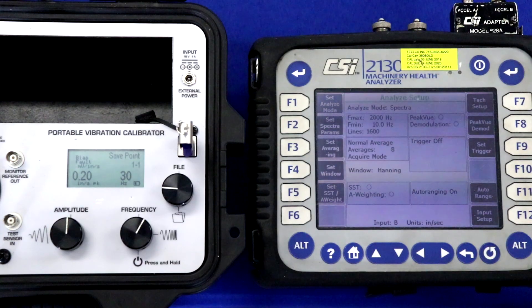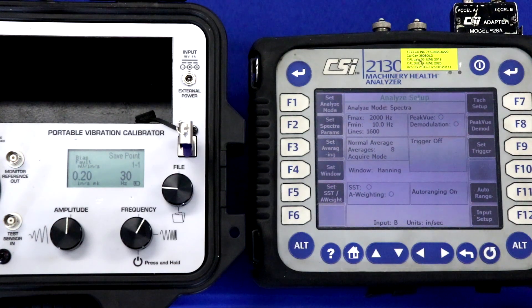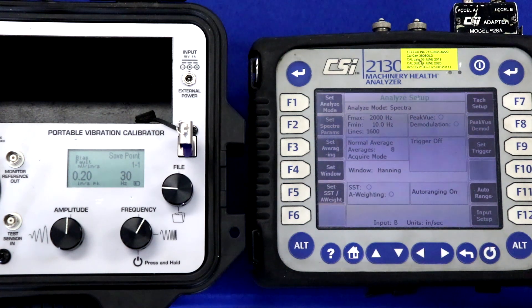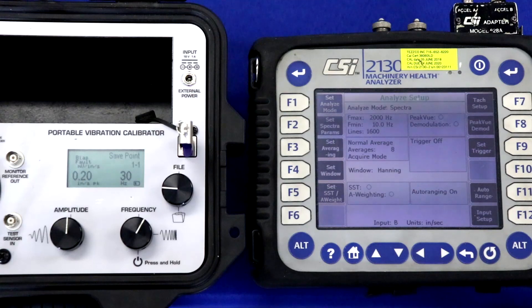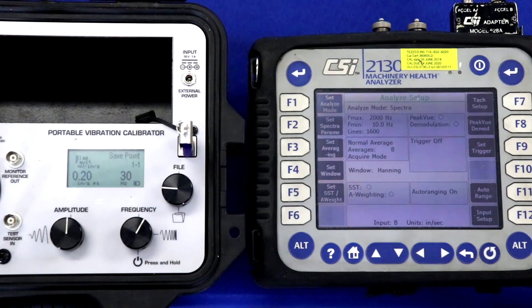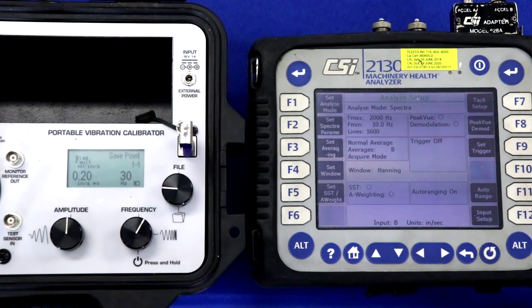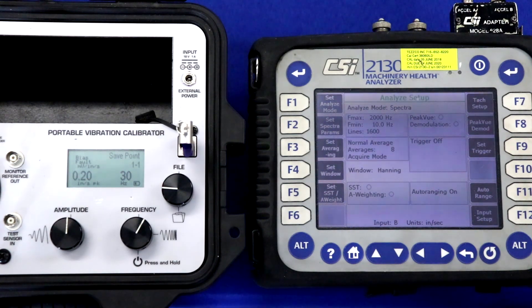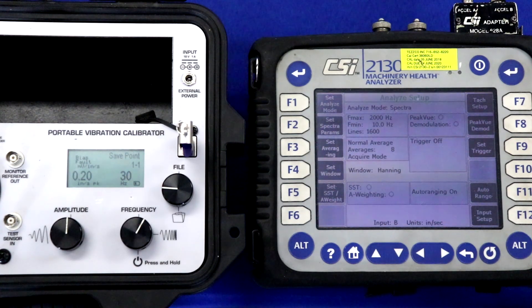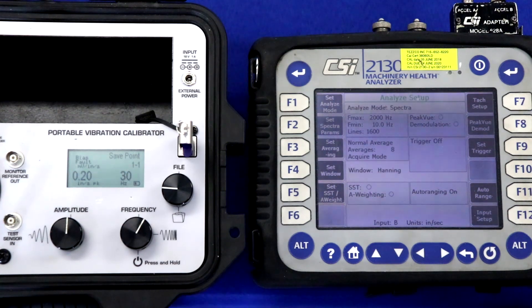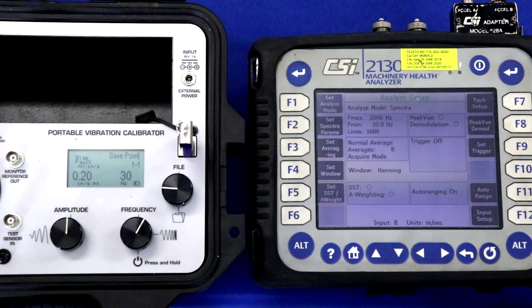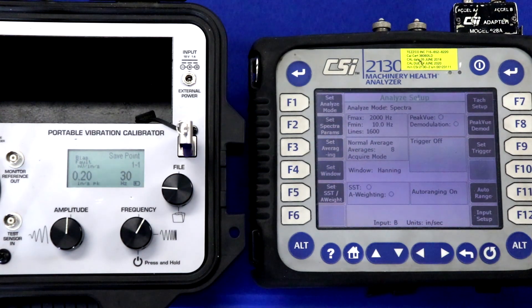We are now ready to calibrate the Emerson 2130 machinery health analyzer. We're going to do a calibration at 30 hertz, which is 1800 cycles per minute, a typical frequency of interest in portable vibration monitoring or route-based vibration monitoring. And we're going to check the analyzer from 0.2 to 1 inch per second for linearity. So a quick five-point test, in this case, just for demonstration purposes, in the real application, you may want to take more test points.